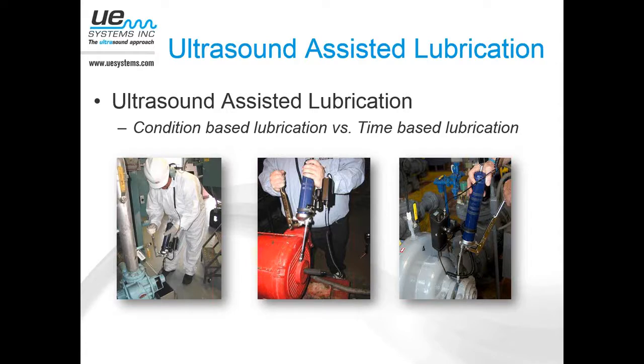We see more and more the interest in shifting over from time-based, which is strictly going by manufacturer's recommendations, this many running hours, this many pumps of grease, and shifting that into several different types of programs. We can shift that into optimizing the time-based. In other words, let's figure out what the correct interval is and stick with that interval. Or we can take it even a step further and go all the way to condition-based. Let's only lubricate when we hit an alarm point that tells us it needs to be lubricated. Other than that, ignore it.